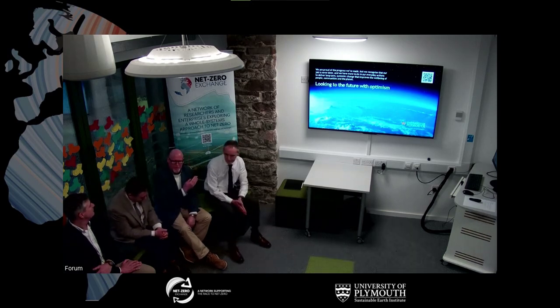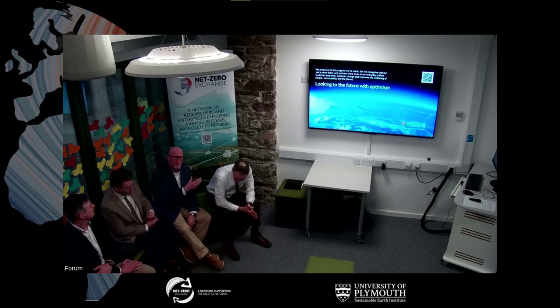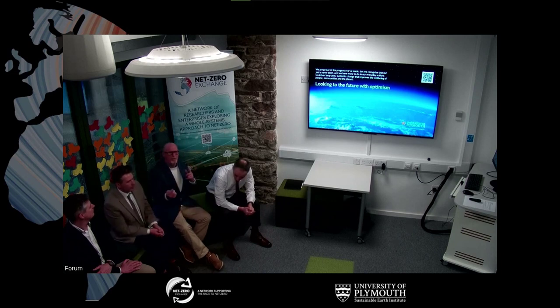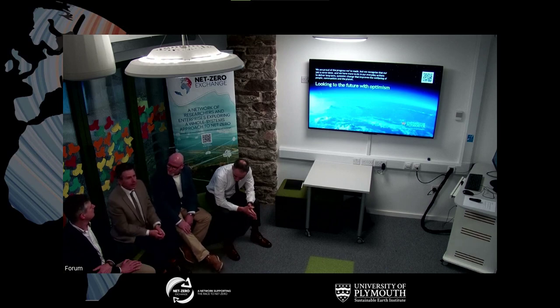As part of the next phase of monitoring, using smart internet-connected technology, we're looking at putting smart probes in the ground in various places to see the effect on growing conditions going forward. When we design everything to an MCS standard, boreholes are kept above a certain minimum temperature, and pipework is buried at least 650 millimetres below ground, with most of it a metre or below, so it doesn't really affect anything growing on the surface. We've got 25 years of experience, and for much of that time, especially the first 10 to 15 years, most installations were in countryside houses, farms and cottages with horizontal pipes, and we didn't really see any effect.